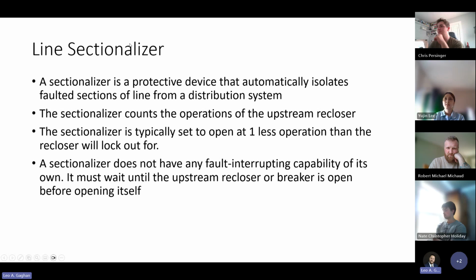Line sectionalizer. It's a protective device that automatically isolates faulted sections of a line from a distribution system. So it's a little bit different than a recloser. I would think of it as a device that is smart, like a recloser, except it doesn't have that fault interrupting capability. So really what it does is determine that the fault happened, but it's going to wait for the voltage to go away. It's going to let an upstream device trip. When the fault current goes away, then it will open. It doesn't have to interrupt that fault current itself. And then the upstream device can reclose and restore that area, and this can stay open if need be.